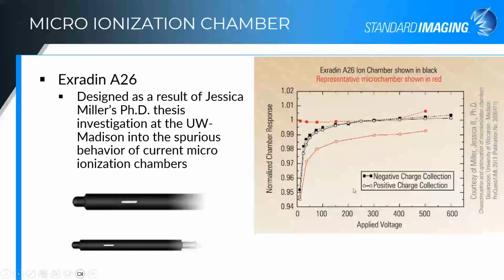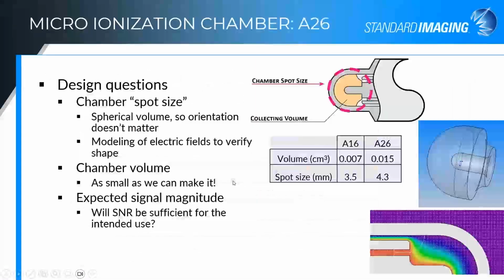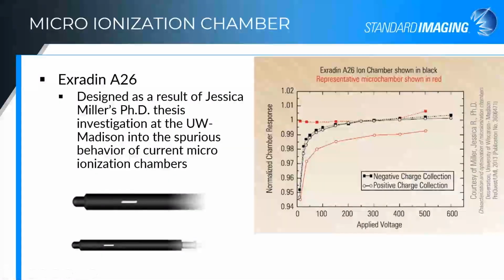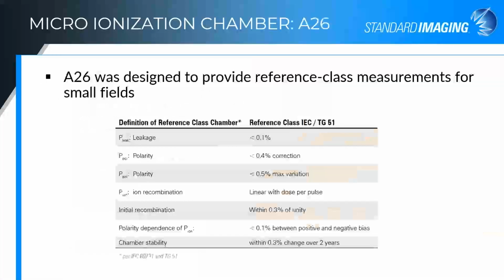chamber response versus voltage plot. And you've got the positive and negative bias overlaying, as you would expect, or as you would hope it to be, where every other microchamber, I should say, had strange behavior where one polarity would be something like this red line and the other polarity would be way down here. That was tracked to really mismatches in the conductance of various portions within the chamber itself, and a change in polarity of the ionization chamber would cause a shift in the electric field lines due to the differences in conductance between mismatched materials in particular, where the A26 now is made completely of the same C552 conducting plastic, and so that's why its behavior is improved compared to some of these other detectors.